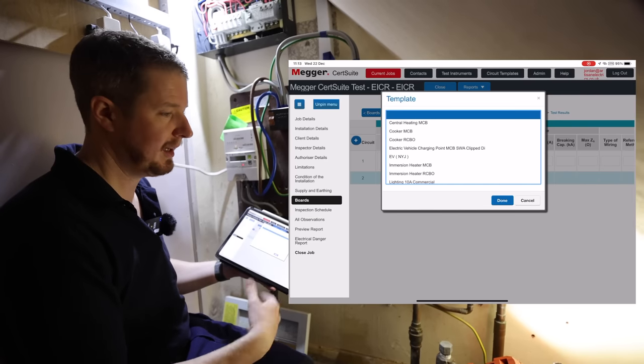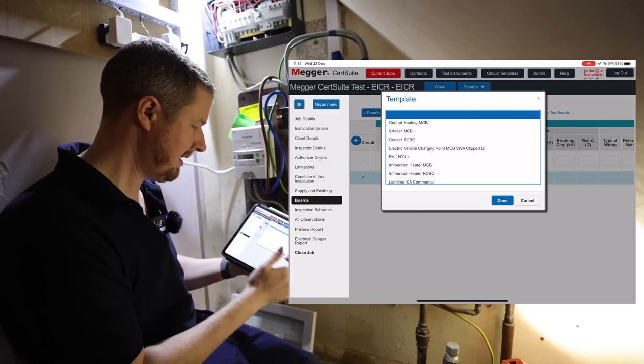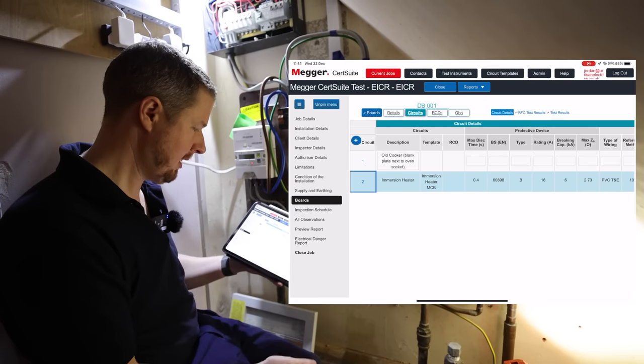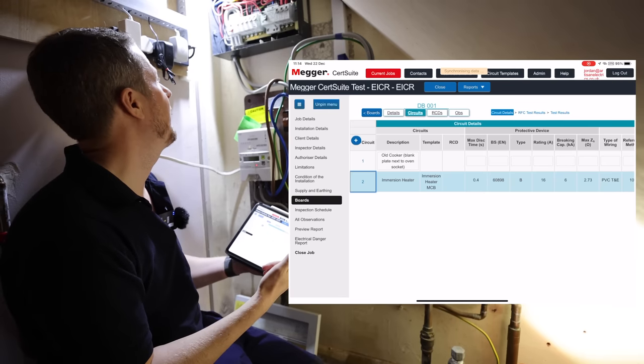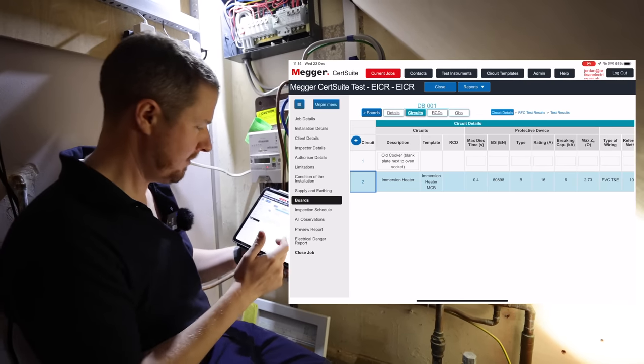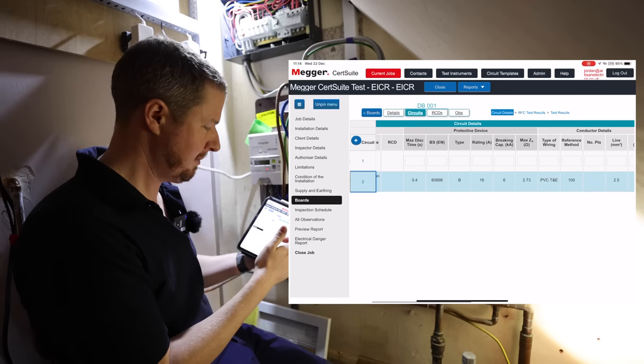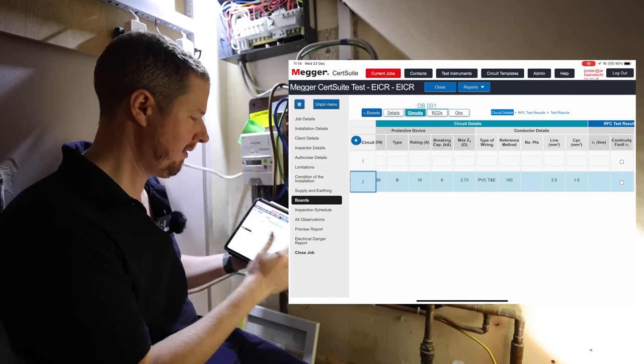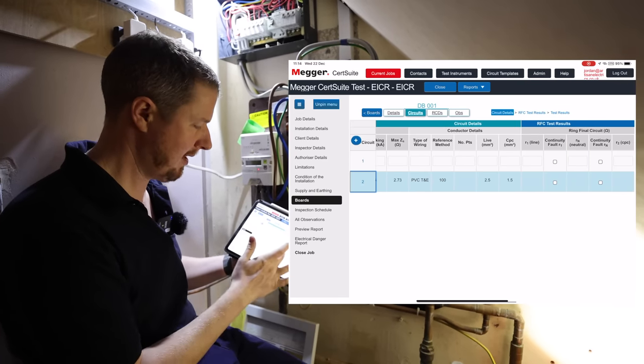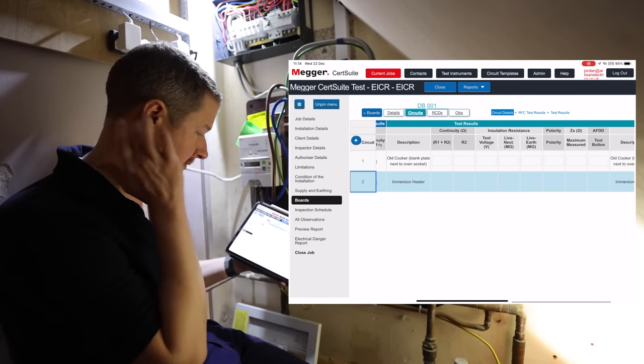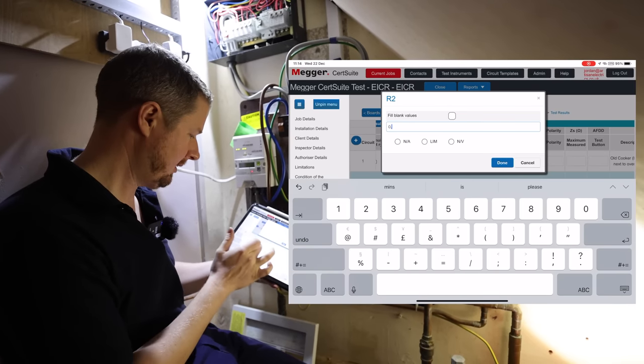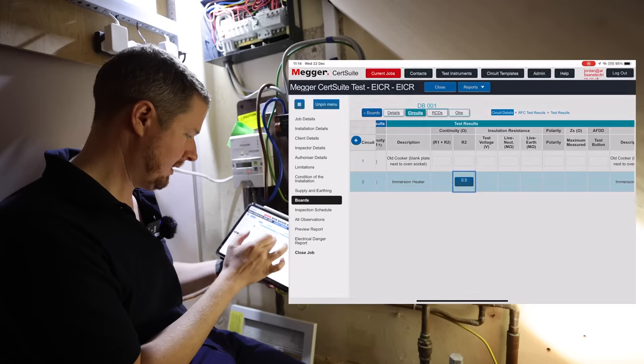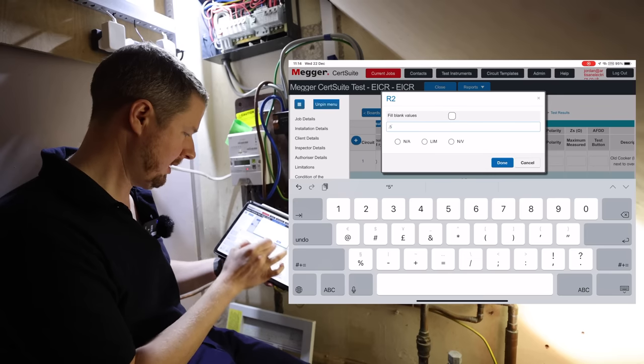That is a 16 amp circuit which says water heater, so that's that spur upstairs, and for this we've got a template. So we've got immersion heater MCB as a template that we've already set up. All the circuits that we use often, like an EV charger circuit, cooker circuit, ring circuit, lighting circuit, we've created a template, and all we do is tap on it, click done, and it fills out all the basic stuff. So we've got that it's a 60898 MCB, which I think it is. We've got the disconnection time, it's a B16, 6kA breaking capacity, max Zs is in there, type of wiring is in there, reference method, everything's kind of in there already. So it just saves us a lot of time. So now all we've got to do is basically fill out the test results. So for example, R2, I did an R2 test, I had like 0.5.